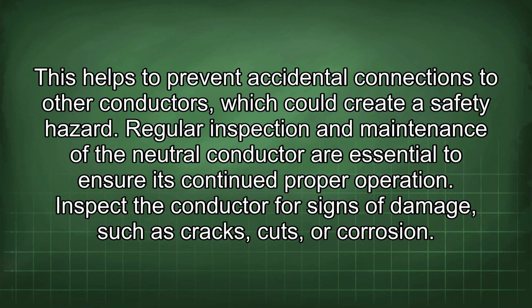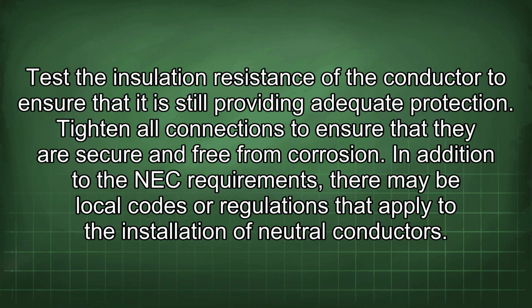Regular inspection and maintenance of the neutral conductor are essential to ensure its continued proper operation. Inspect the conductor for signs of damage, such as cracks, cuts, or corrosion. Test the insulation resistance of the conductor to ensure that it is still providing adequate protection. Tighten all connections to ensure that they are secure and free from corrosion.